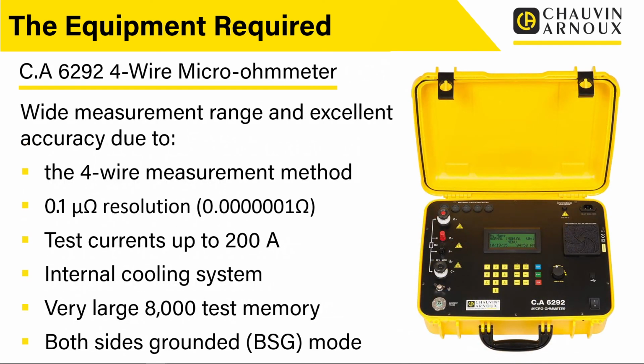Moving up to the big boy now. This is the top of the range micro ohm meter that we've got. This is the 6292, and this is a 200 amp micro ohm meter. So we're going from 10 amps up to 200 amps in this case, and this is a sort of production level type tester, which I think will actually do 100 amp tests indefinitely. There's no sort of heating cycle on that.